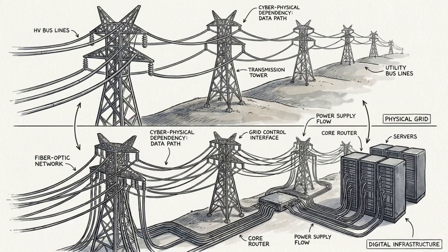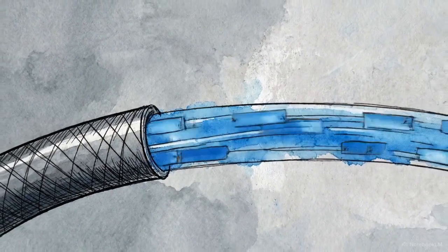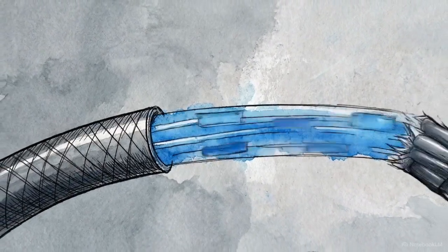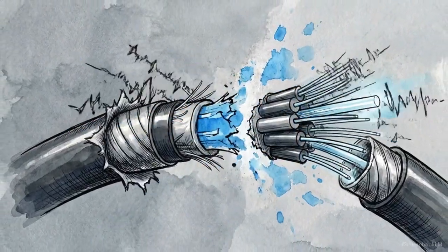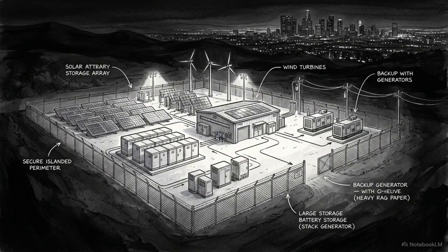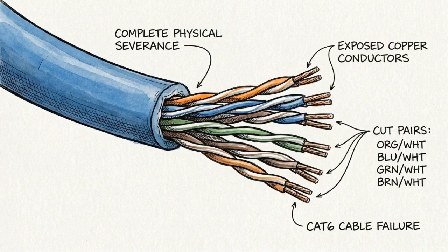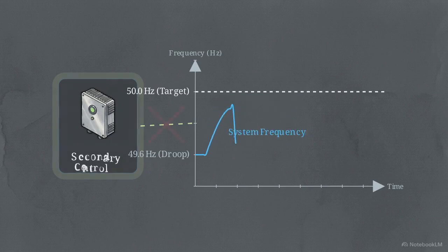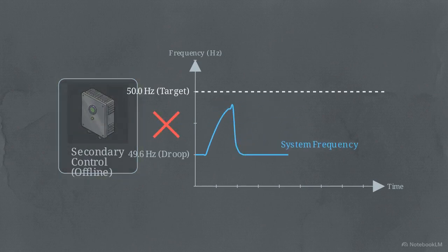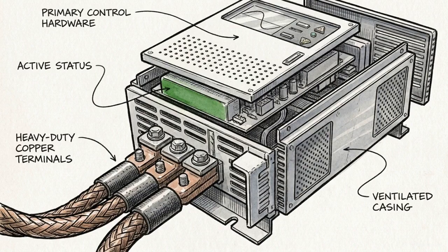Microgrids are cyber-physical systems, meaning the flow of electricity is dependent on data networks. This introduces vulnerabilities. If data packets are delayed, or if set points are manipulated, the system voltage and frequency will destabilize. Consider the ultimate stress test. The microgrid is operating in islanded mode, and the primary communication link to the inverters is severed. Without that link, the system loses its secondary control, the ability to coordinate the recovery of the frequency back to a perfect 50.0 Hz. However, the foundational layer, primary control, remains intact.